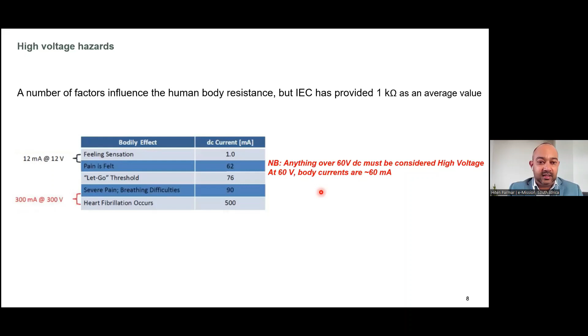We can see typical technical reference values around 60 volts and 60 milliamps, where this becomes a health and safety issue. This is key to note across the board for these systems. We've also seen in earlier presentations that storage systems are now going into high voltage areas well above 300 volts, which is certainly something to note for health and safety.